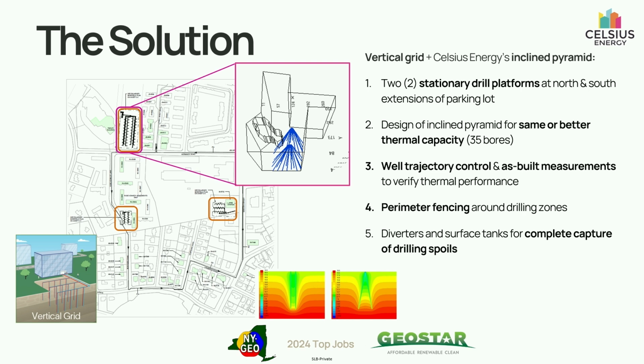On those 2 platforms, once again one furthest north, one furthest south, you see the image in the pink square. We also designed that inclined pyramid solution with same or better thermal capacity. We reduced those 60 original vertical grid bores down to a total of 35 bores. That was done through significant sophisticated modeling, validation with the engineer of record, CDM Smith, reviewing and ensuring that yes, we could bring 60 bores down to 35 by getting much greater well spacing and an improved completions configuration. So we moved to a quad loop or double U-bend assembly, getting 80-foot separation on a per bore perspective as opposed to the original design of 25-foot spacing.